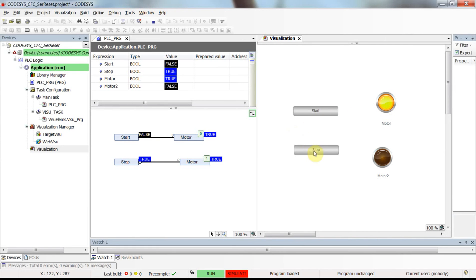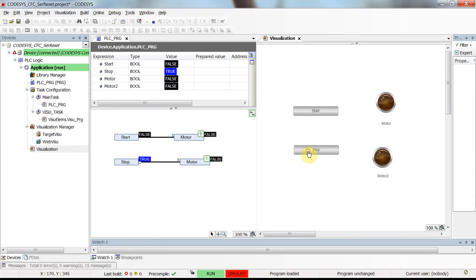If I click on stop, the value of stop becomes false. Since we have the negation here, the input to the Reset motor becomes true, and as a result motor resets. So in normal operation: pressing start sets the motor, pressing stop resets it.